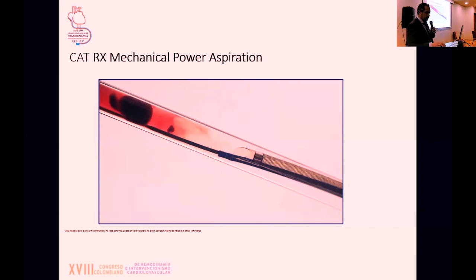So step by step, how to use it. Again, it's an 014 catheter, so it's an 014 wire. It's an RX, rapid exchange, so you can use your traditional 180 wire. You turn it off when you hook it up, and you turn the console on. In the console, you'll see 4 different lights that you have to have all up and running before you can put the catheter in the body. When you put it in the body, the recommendation is to put it proximal to the clot, turn it on, and just sit there for 30 seconds.